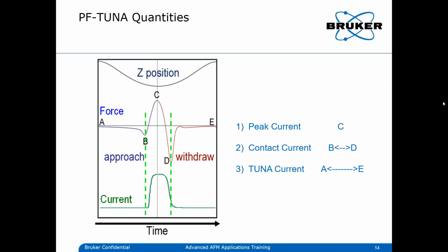What can we measure in Peak Force TUNA? It uses the peak force technique, where we have a forced oscillation at, let's say, 2 kilohertz or down to 0.125 kilohertz. So your tip is moved not at a resonance frequency, but much, much lower. You press onto the surface until you reach certain stable conditions, a good contact with the surface, but without being too aggressive. So it's much less aggressive than contact mode, and also much less aggressive than tapping mode.